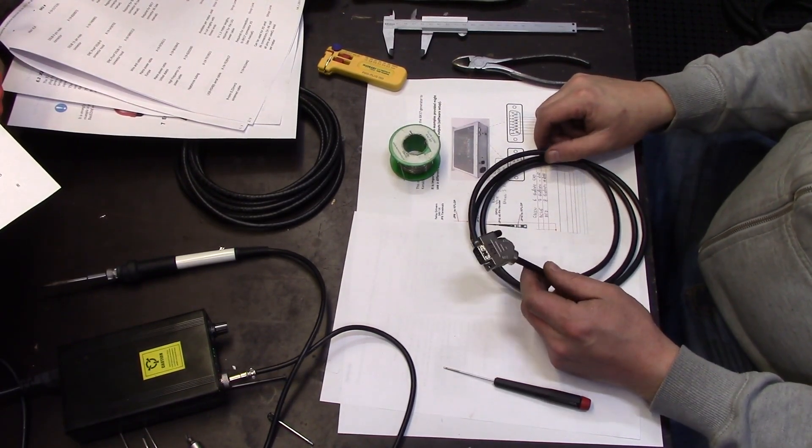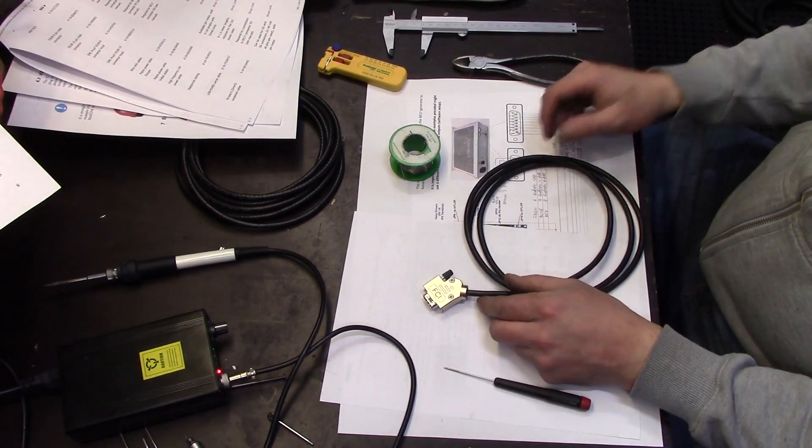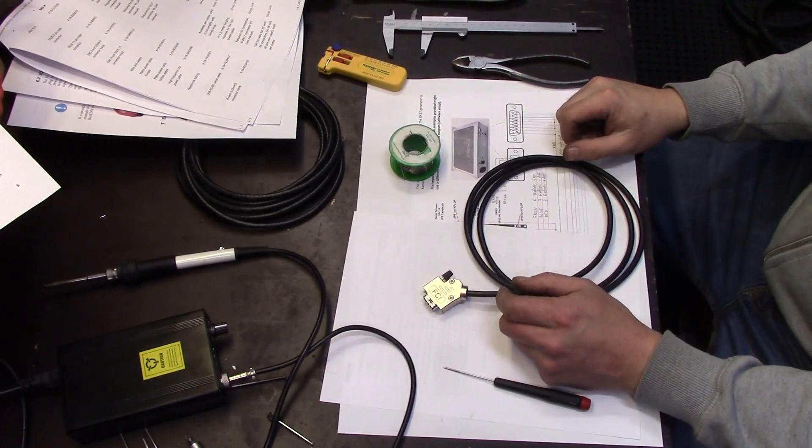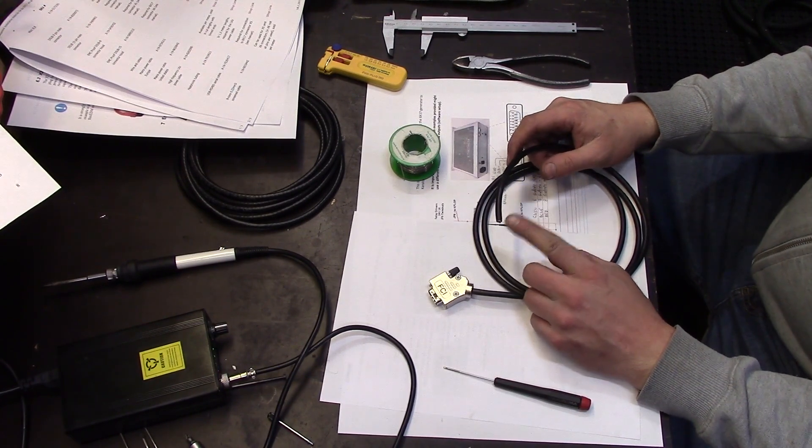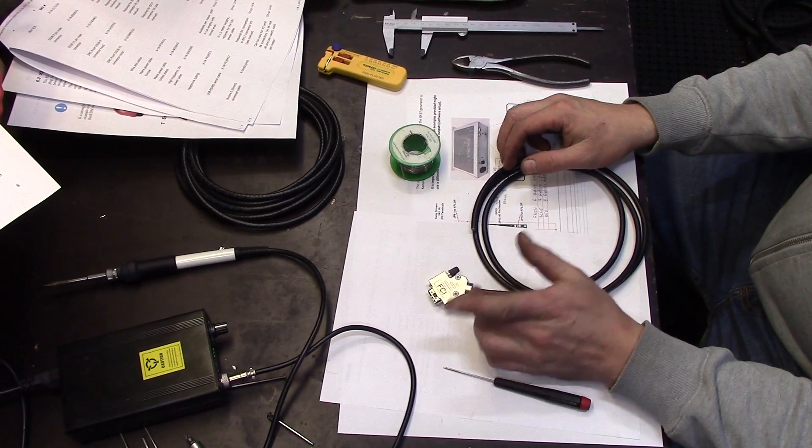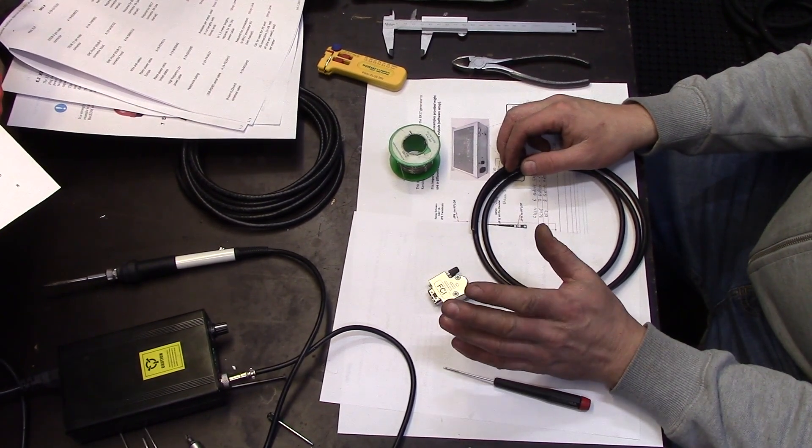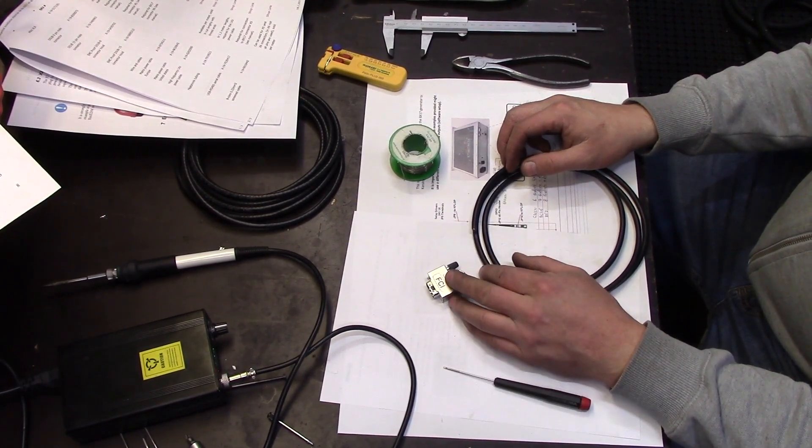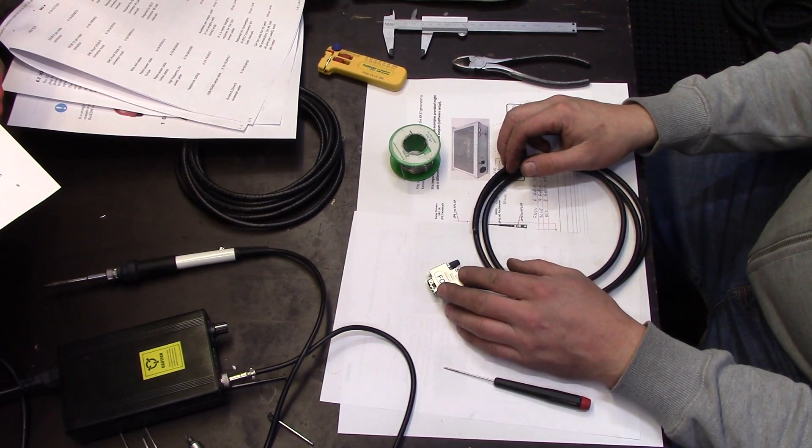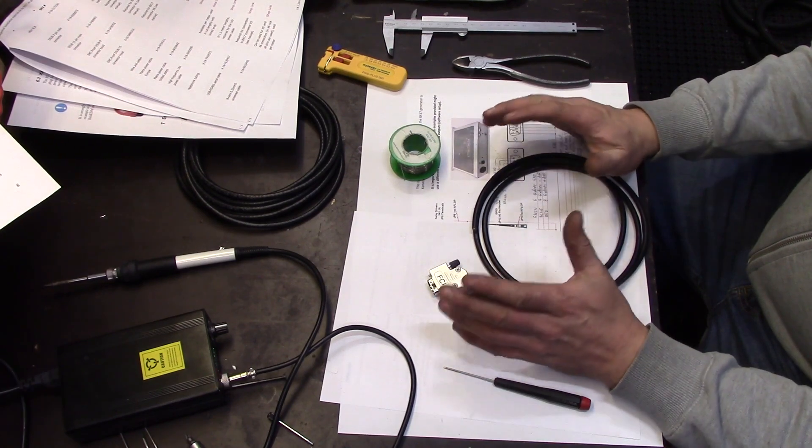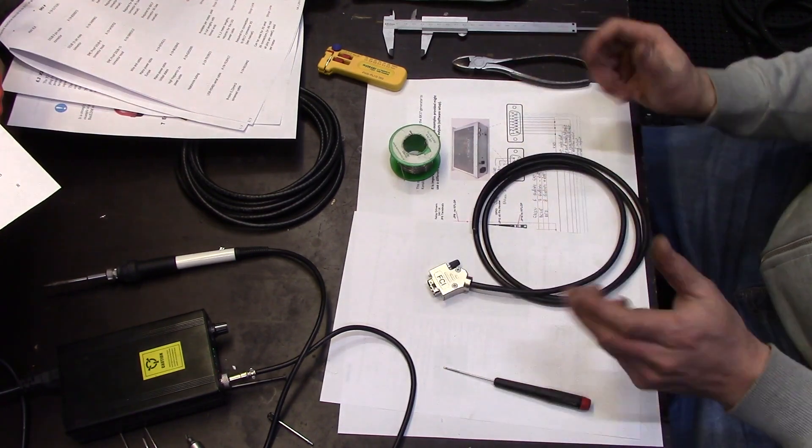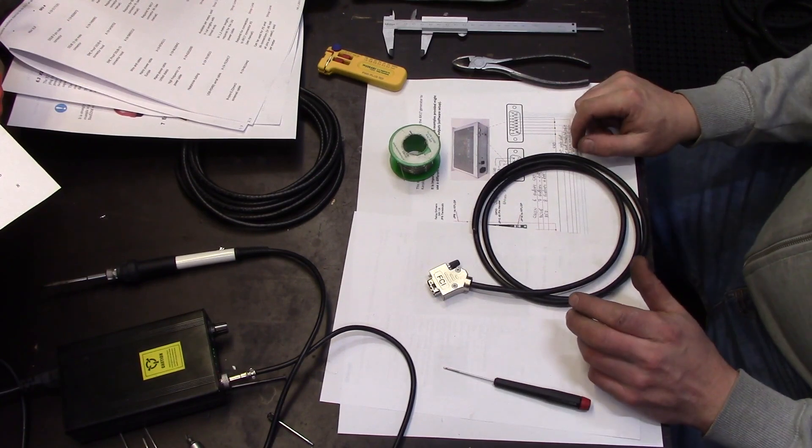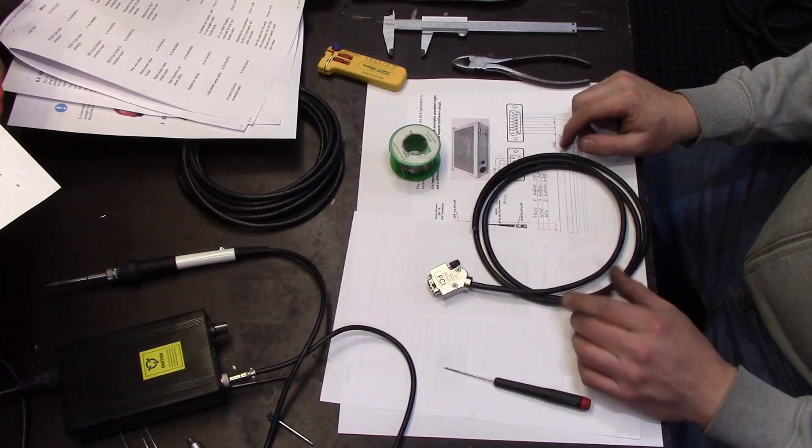So that's one data cable done. I have to remember at the other end the shielding should not be connected to anything. It's only connected at the end of the generator. So that there's no ground loops. I'm kind of keeping the generator as the ground point.